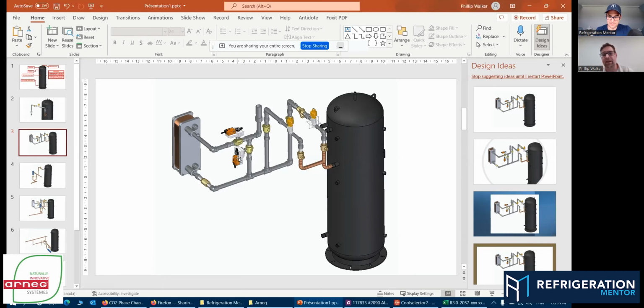Even in oil separators, if you have suction groups and you have multiple separators coming into a manifold, if those separators don't have check valves, gas is going to migrate backwards and is going to condense in those inoperable separators. So hence check valve, we don't want gas coming through there. And we're going to come right out and we're going to feed our high pressure expansion device here. Okay. Trevor, any questions on that? No, I think that's perfect. It makes a lot of sense to me.